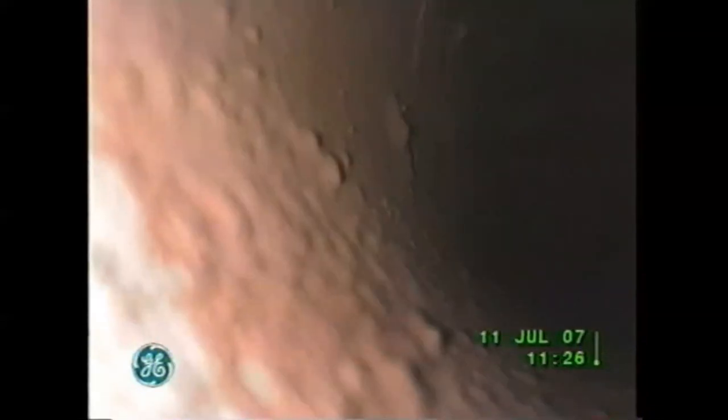Now, occasionally, you'll see a place where it's cracked off and you can see some bare metal. But the rest of that stuff, that whole area is coated. That's insulation. Makes it hard to transfer heat. You're burning all that fuel, those hot gases are on the outside of that pipe, that pipe's full of water, and you're wanting to generate steam inside that pipe. Some of them are probably no more than 3-inch diameter.